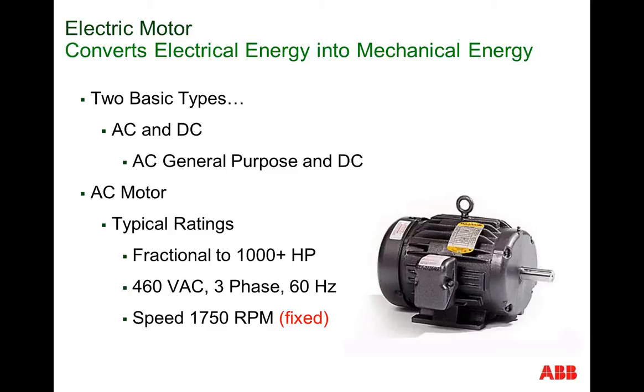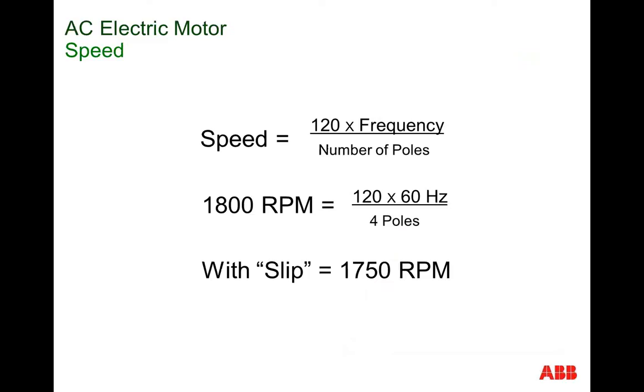Now, there are two basic types, AC and DC. The most prevalent is the AC motor. Its horsepower, or its force, or its strength, ranges from fractions of a horsepower to thousands of horsepower. The typical motor operates at 460 volts, three-phase current, and has a fixed speed of 1,750 revolutions per minute, or RPM.